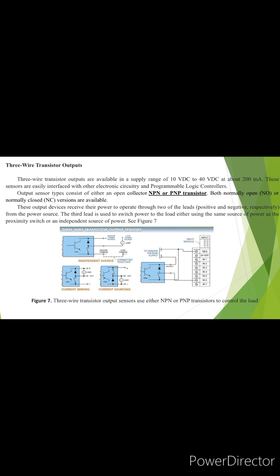Three-wire transistor outputs. Three-wire transistor outputs are available in a supply range of 10 volts direct current to 40 volts direct current at about 200 milliamperes. These sensors are easily interfaced with other electronic circuitry and programmable logic controllers. The output sensor type consists of either an open collector NPN or PNP transistor, and both normally open and normally closed versions are available. These output devices receive their power to operate through two of the leads, positive and negative respectively, from the power source.